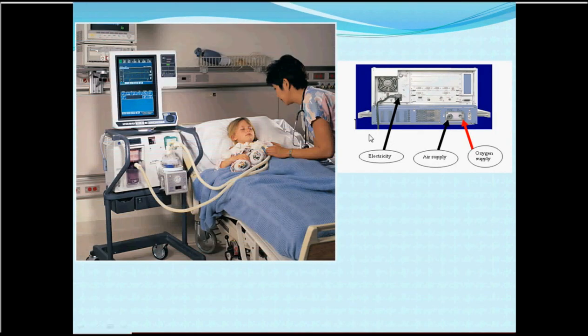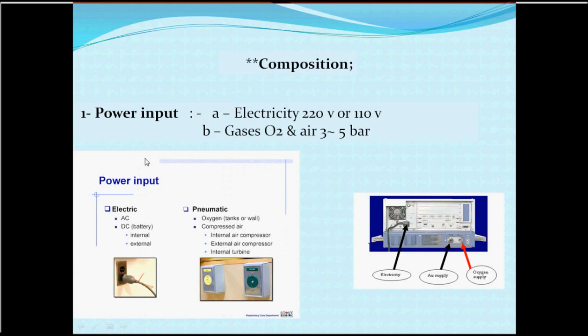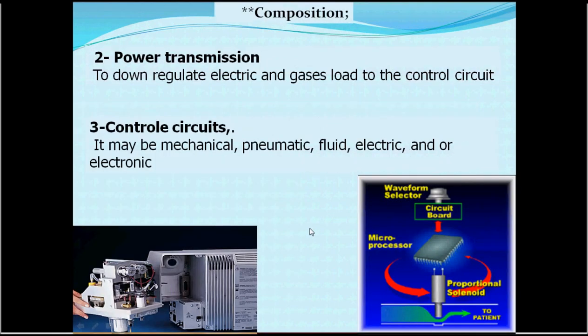These are the inputs for the ventilator: it runs on electricity and is supplied with air and oxygen in order to deliver pressure to the patient. The composition includes a power socket for electricity, and two other sockets with different colors — one for oxygen and one for air. The electricity and air are supplied at high voltage or high pressure, and these are down-regulated to match the requirements of the control circuits, which may be electric, electronic, pneumatic, or fluid-based.